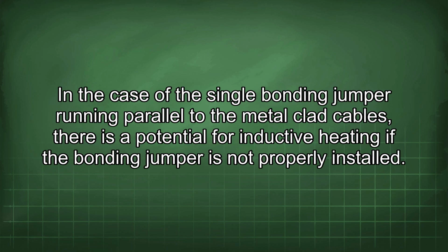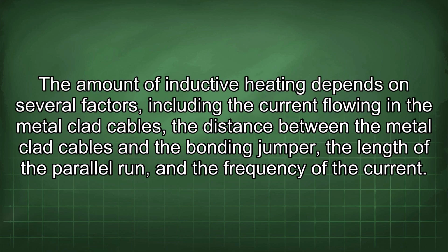In the case of the single bonding jumper running parallel to the metal-clad cables, there is a potential for inductive heating if the bonding jumper is not properly installed. The amount of inductive heating depends on several factors, including the current flowing in the metal-clad cables, the distance between the metal-clad cables and the bonding jumper, the length of the parallel run, and the frequency of the current.